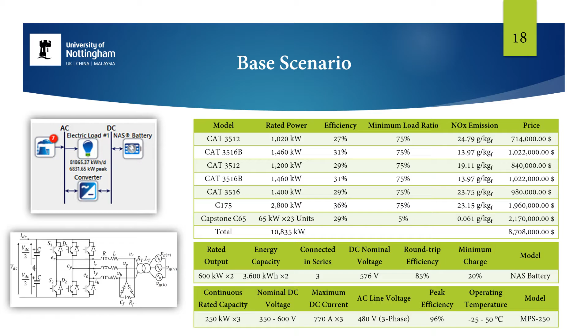In terms of the waste heat recovery system implemented in scenario 1 to scenario 4, a waste heat recovery was configured in all suggested scenarios. For providing the possibility of heat recovery, 2 options were presented in this study. Either replacing all generating units with a built-in CHP generator, or the compact, such as a small scale compact version that we reviewed in the background slide, or installing external heat recovery systems such as plate heat exchangers and a structure to flow the exhaust gas of generators to the recovery facility and then for further cleaning processes.